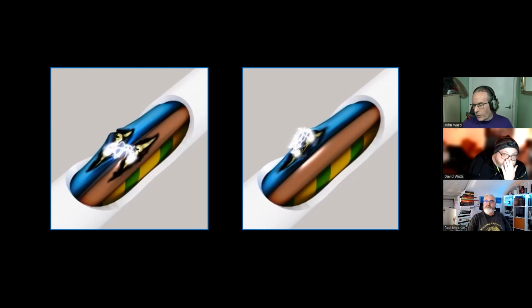And on the right there, we've got just an arc on a single conductor. On the left, it's called a parallel arc fault as it's across two conductors. And the other one is a series arc. It's basically where conductors come apart and it's just arcing between the two ends.